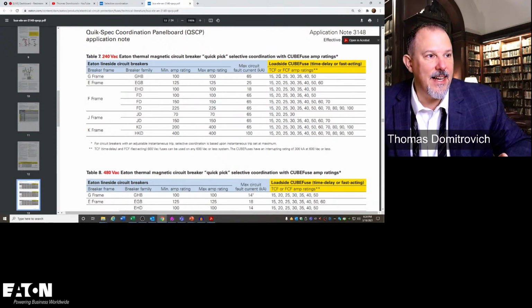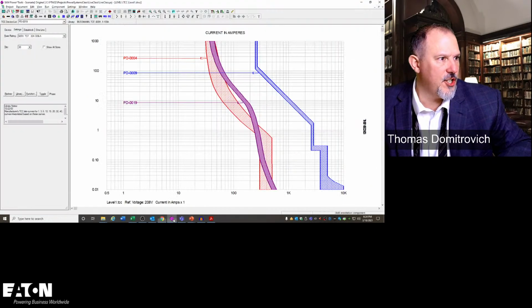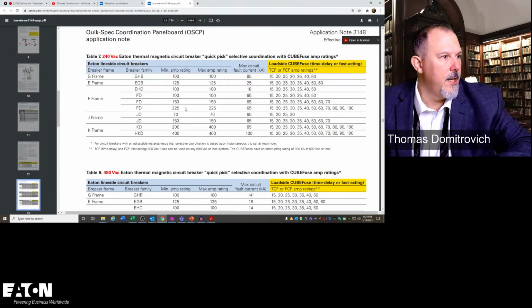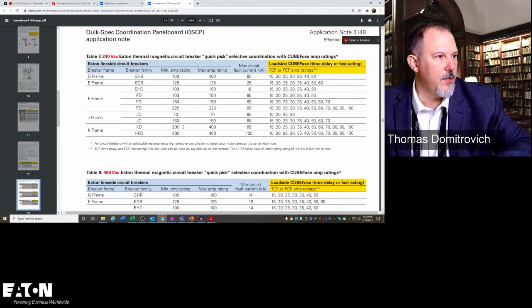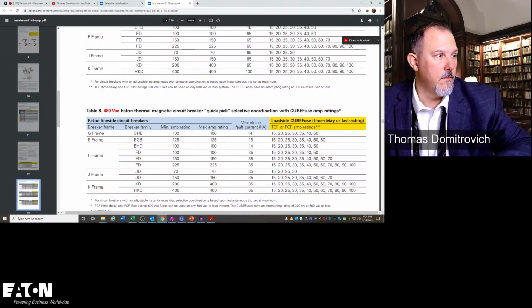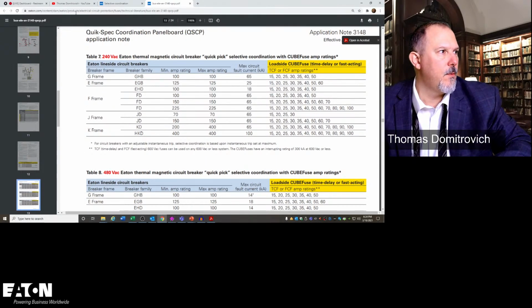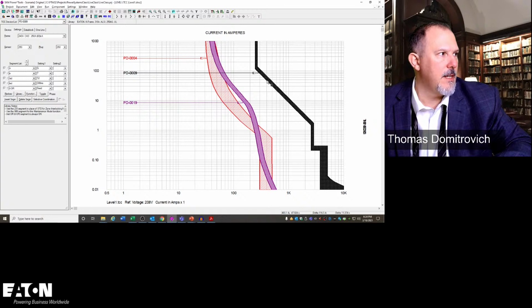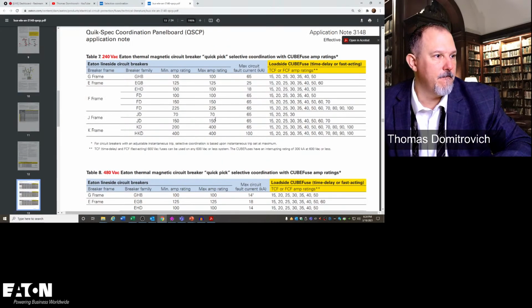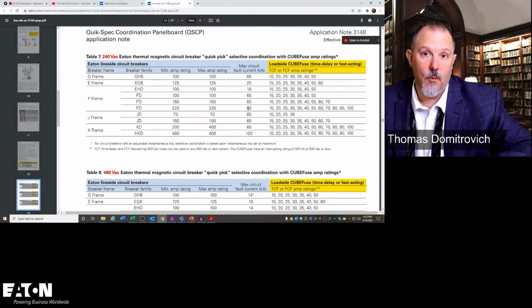Let's say I have a TCF. I had a 30 amp fuse. All of these have 30 amp fuses. I needed 250 amp, right? Check it, 250 amp fuse, upstream breaker. I've got a 200, maximum 400, 225. So K-frame. That's at 240 volts. What do I have? I have a K-frame breaker, right? But this is an electronic trip unit. A K-frame breaker goes up to 400. If I made it a 225 amp, I could put an F-frame breaker in there. If I had it as a 225 amp panel board, I could put an F-frame breaker in there. Selectively coordinates up to 65,000 amps. Why? Why is that the case?